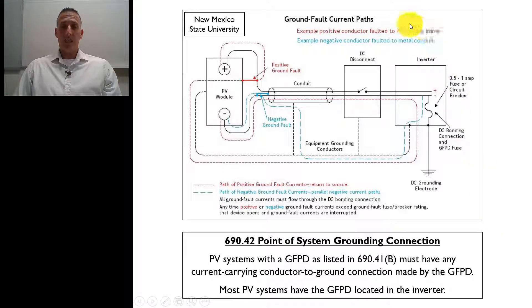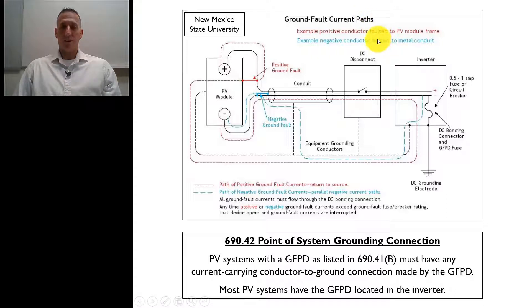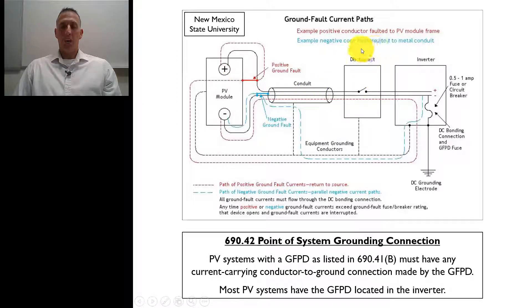If you take a look at this image right here, this is outlining and helping us understand the ground fault current paths. This is a representation of a solar PV system. Right here you can see the PV module or modules — this is our array. Here we have our conduit, here we have the DC disconnect, we have our inverter right here, and then we have our DC grounding electrode and then our grounding electrode conductor right here.